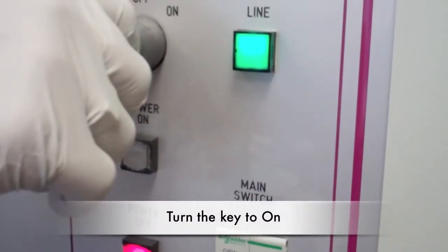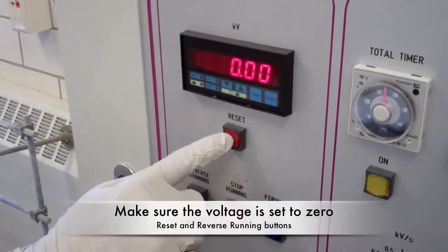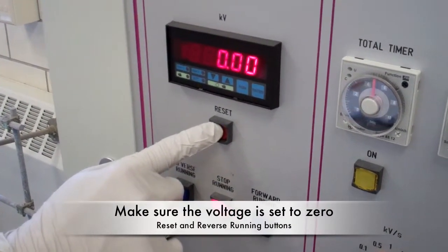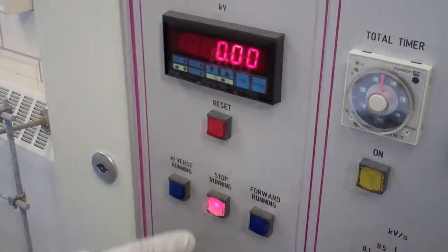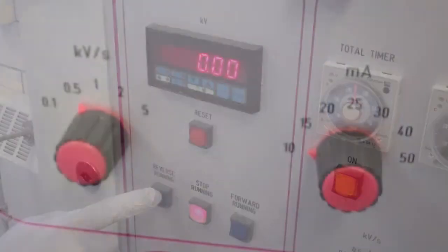To begin the test, turn the key to the on position. Make sure the voltage setting is set to zero. To check this, press the red reset button to reset the digital output to zero. Also press the reverse running button to return the voltage knob to zero.